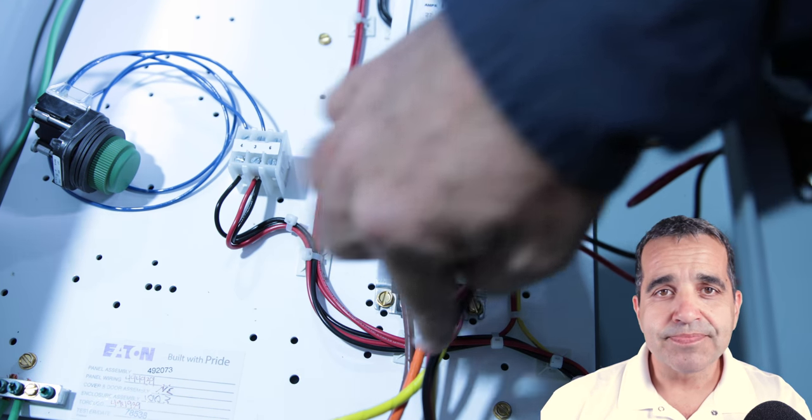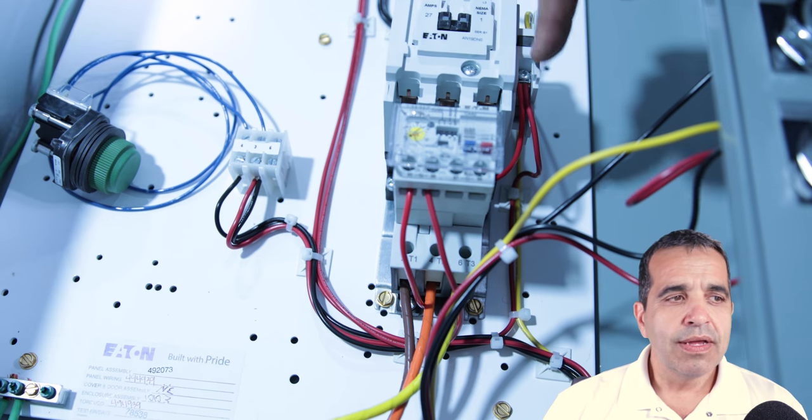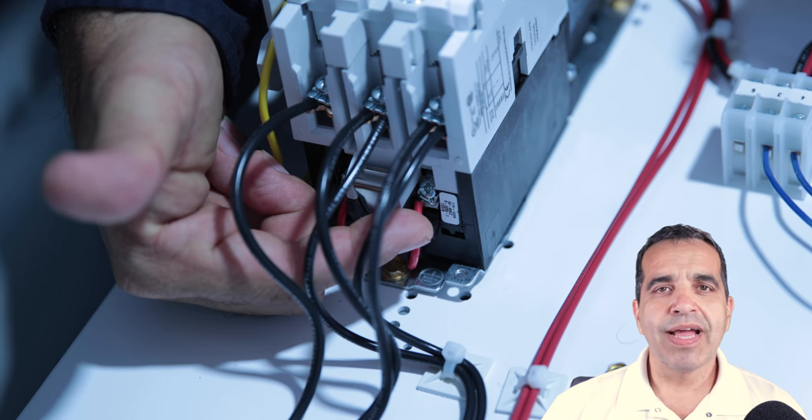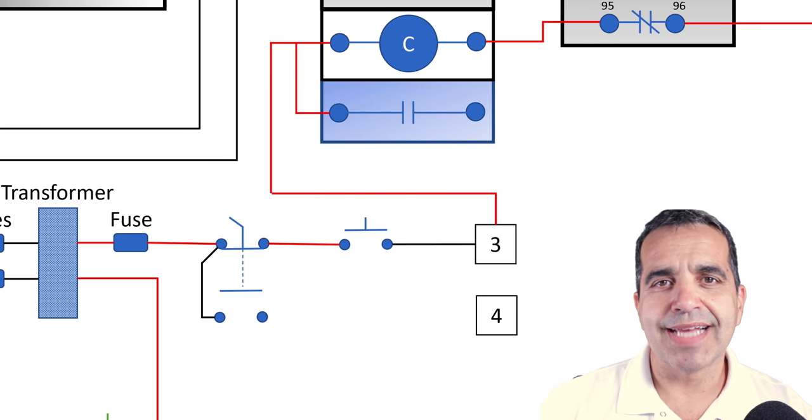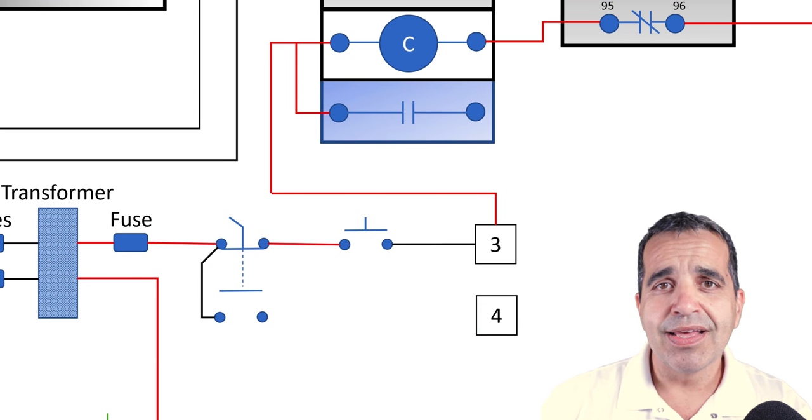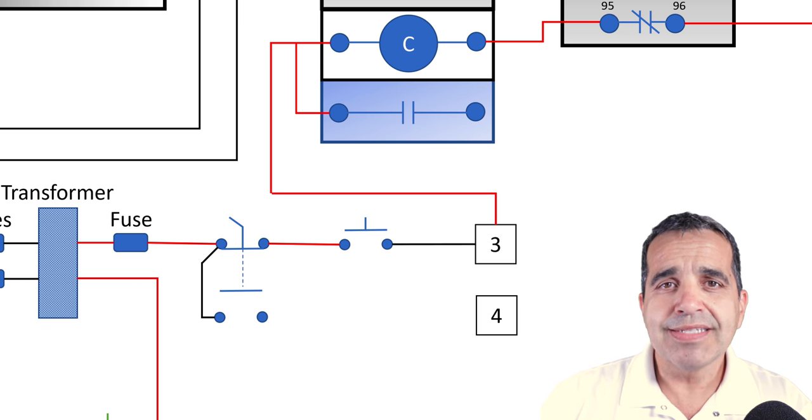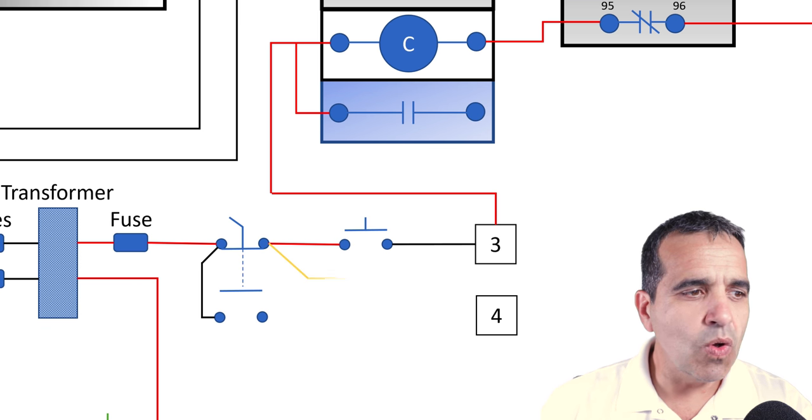We have a little jumper from our coil over to one side of our normally open contactor. Then we need a holding contact so that after we push the start button, our coil and our contact can remain closed.